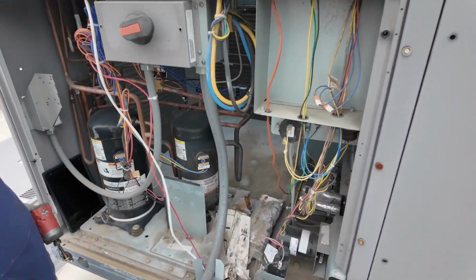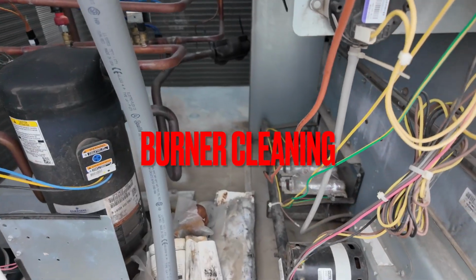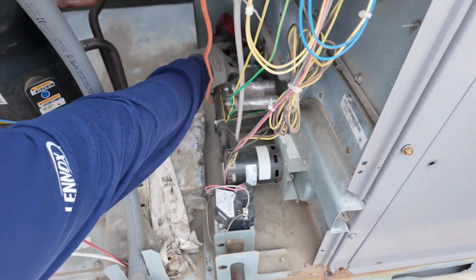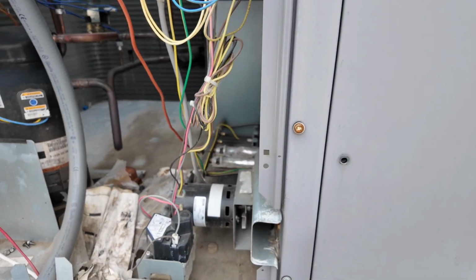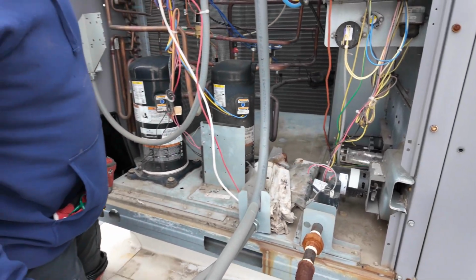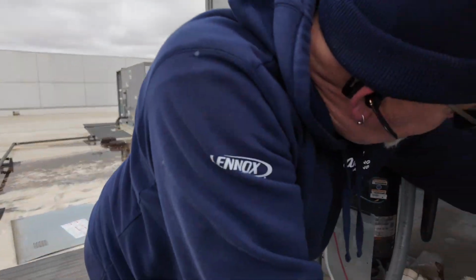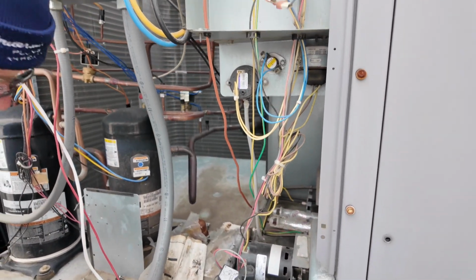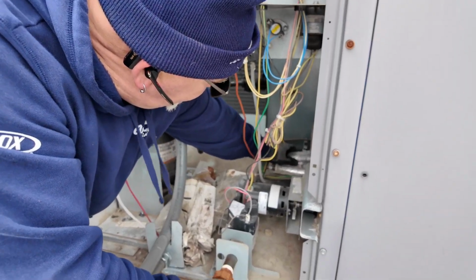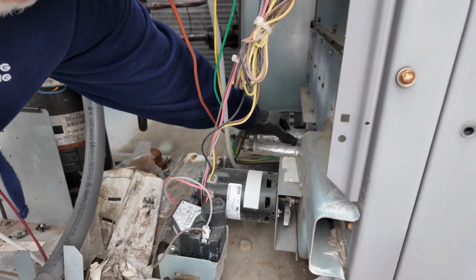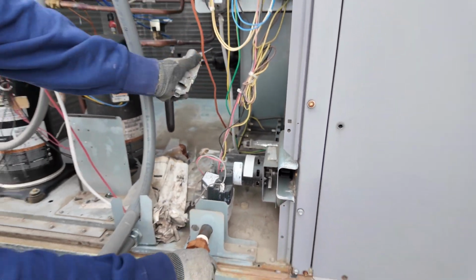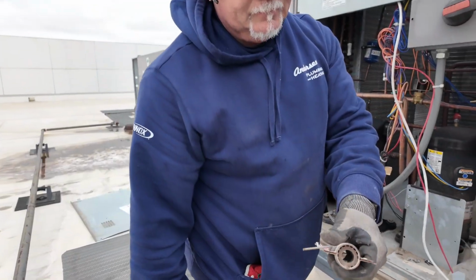So one of the other things that we're gonna do is once we get all the burner tubes out, we're gonna clean the flame sensor. What the flame sensor does is it proves to the circuit board in the unit that not only did we attempt to light a fire, but that we actually lit the fire and it was a successful ignition. So if that flame sensor doesn't read that the ignition was successful, the unit will go into what's called a lockout, and it'll basically shut itself down to prevent gas flow that's unnecessary.